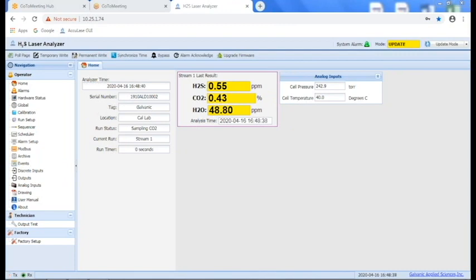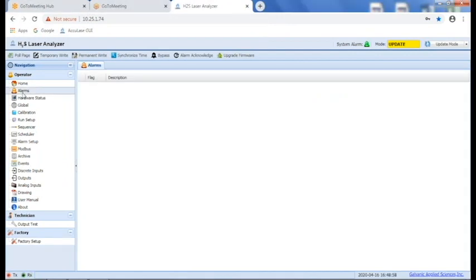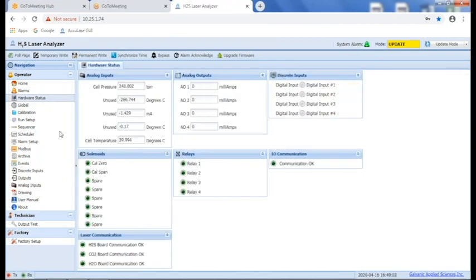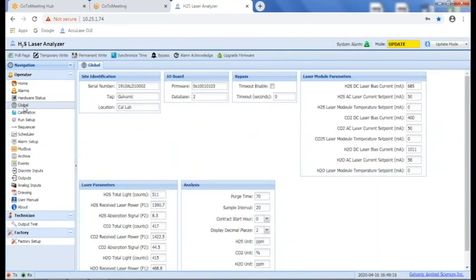Along the side here, there are several items related to operation. I'll go through them relatively quickly. We have an alarms page, which allows us to view fault alarms and concentration alarms. We have statuses of various pieces of hardware. If you want to have a look, you can see what your analog outputs are doing or what relays are active. The global page has some general information about the analyzer.